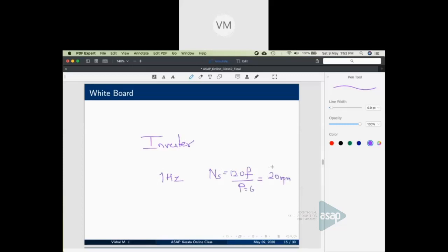That's why the rotor did not have enough time to react. It was only 10 millisecond. Now it is only 20 RPM, which means the rotor now has enough time to react to the positive torque, and the rotor builds up speed. Now as it builds up speed, change it to 2 Hertz, then 3 Hertz, like that build up to its rated value of 50 Hertz. So since we have an inverter which can vary frequency through frequency modulation, I do not need starting dampers. Okay, so this pretty much sums up the true synchronous mode of operation.